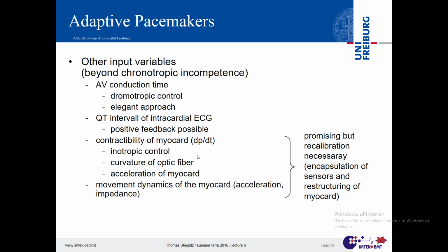Of course, it would be nice to see how the muscle contracts, so how the pressure changes over time. That will mean you have to put something into the ventricle to measure that. And I'll show you some ideas that person had. One could be a pressure transducer, which is not bad, but you need at least 2 additional cables, probably more, because you need voltage and ground and signal. You have to modulate things on top of that.